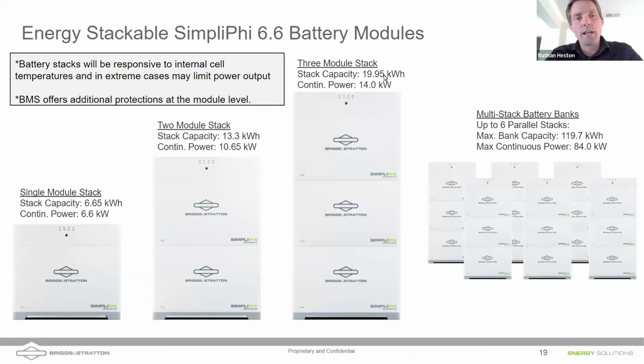So here's what I was getting at with the overall power capabilities of these batteries. In a single module, a single stack, this battery can output at 1 C. That means a full discharge in a single hour. If we stack these batteries up, we have to be a little bit more careful about balancing, making sure that the bottom battery is doing as much work as the top battery.